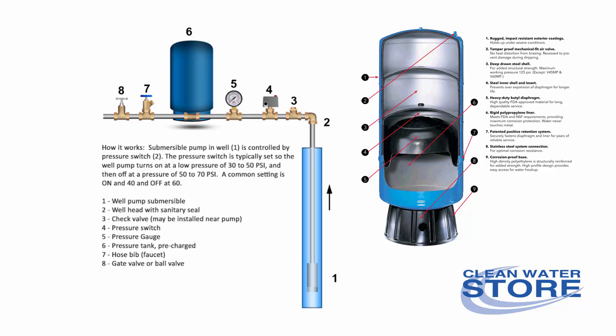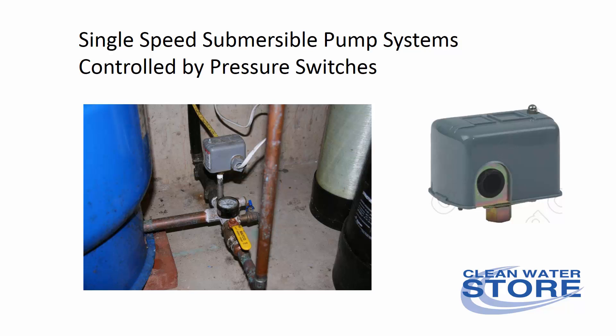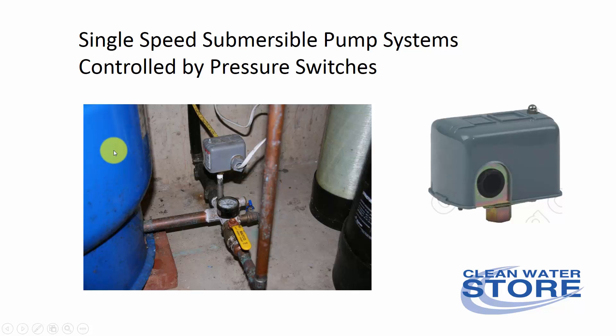Here's how it works. Submersible pumps in the well are controlled by a pressure switch. The pressure switch is typically set so the well pump turns on at a low pressure and off at a higher pressure. A common setting is on at 30, off at 50, or on at 40, off at 60. These systems are single speed submersible pumps. Here you see the pressure switch, pressure gauge, and a single pipe going in and out of the pressure tank. Water coming from the well flows into the pressure tank, builds up pressure, and then the pressure switch shuts off the well pump.